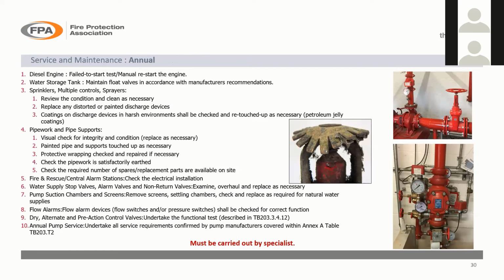I'm not going to read them all out because they are in TB 203, which you can get a copy of from RISCAuthority website. By the way, I didn't point that out, but you can actually get a copy of that and read through that in some detail. But on the annual service, it must be carried out by the specialist. But on this one, you can see things like the visual integrity check of the condition of the pipework and the pipe supports and sprinkler heads, things like that.